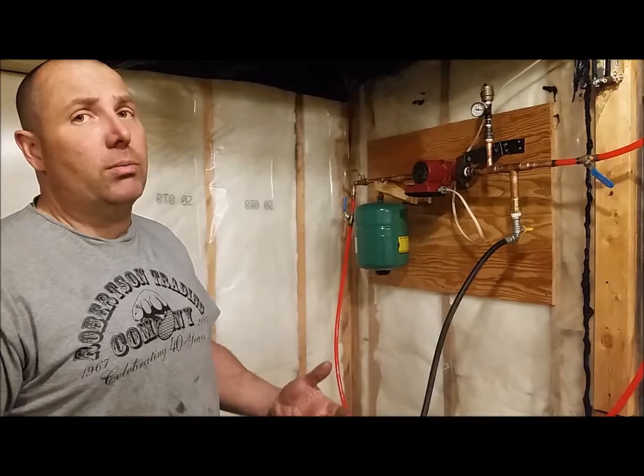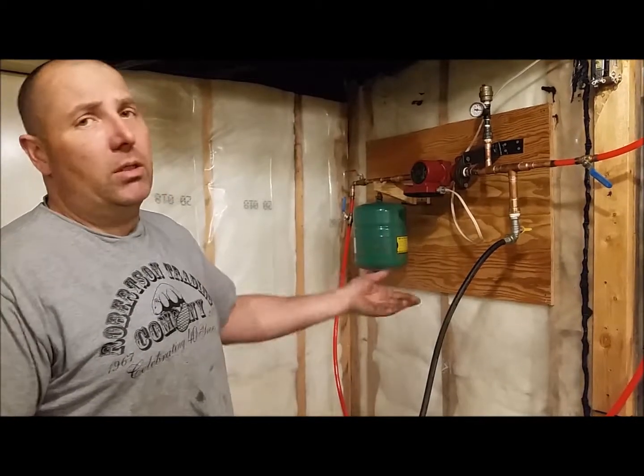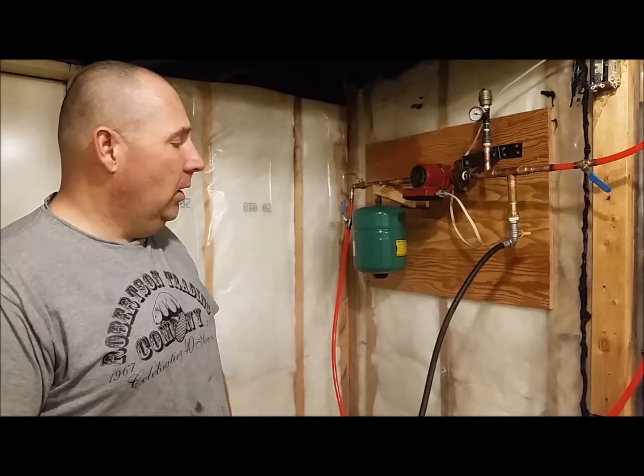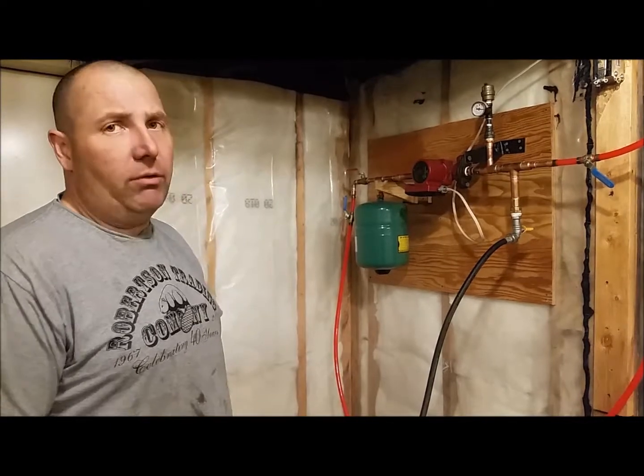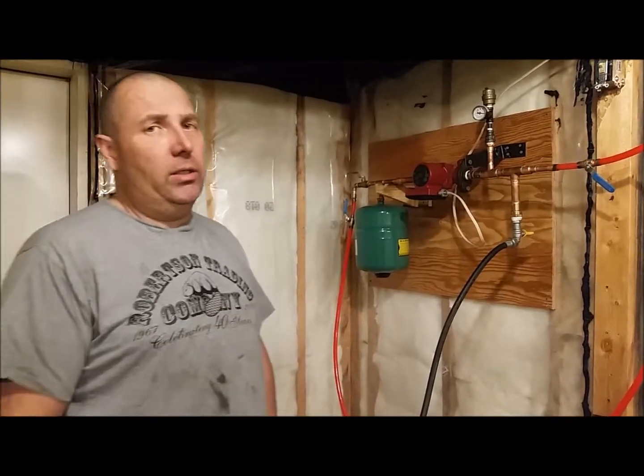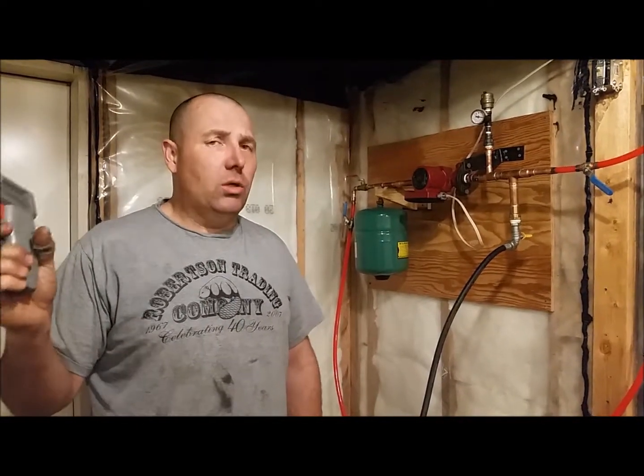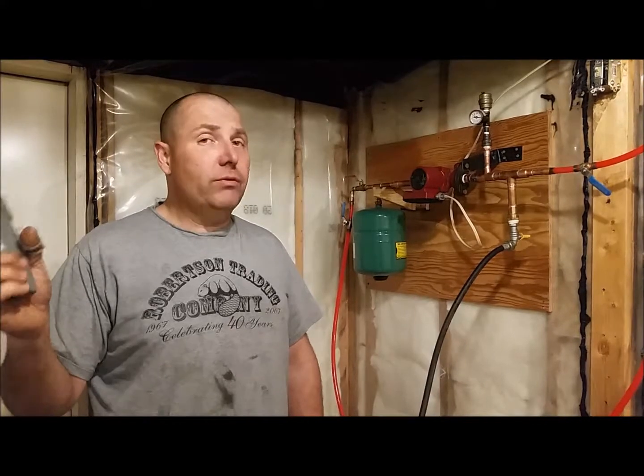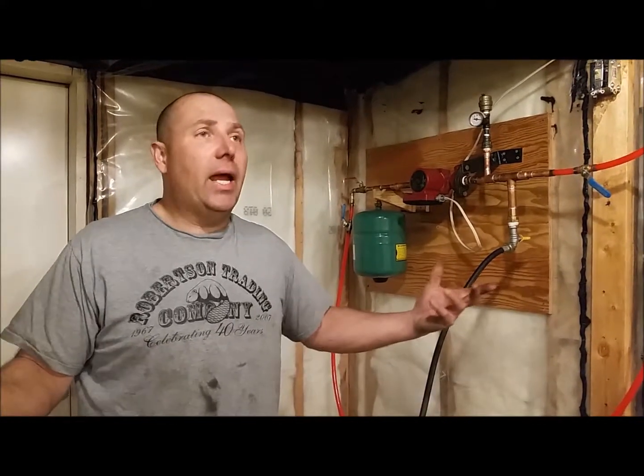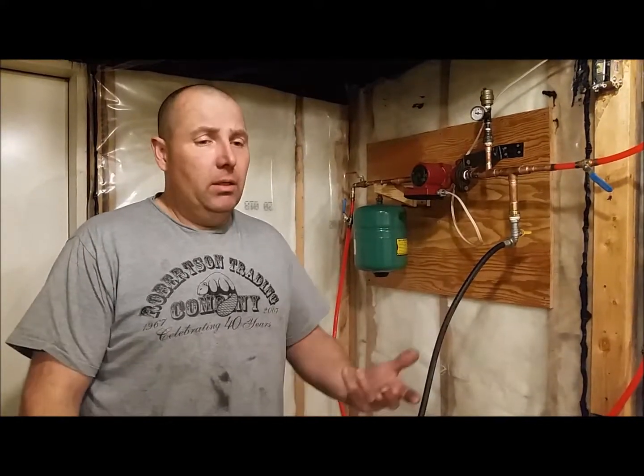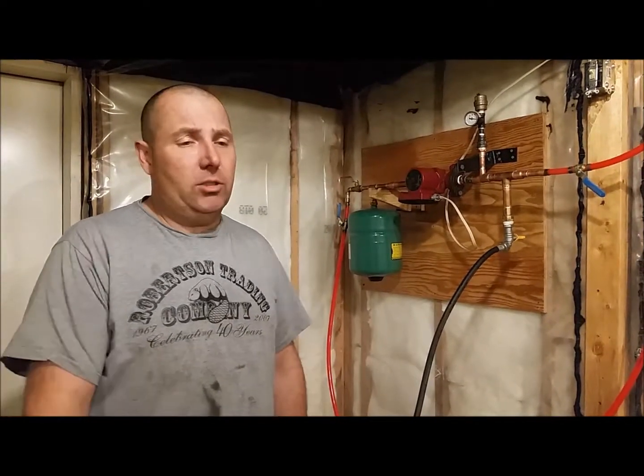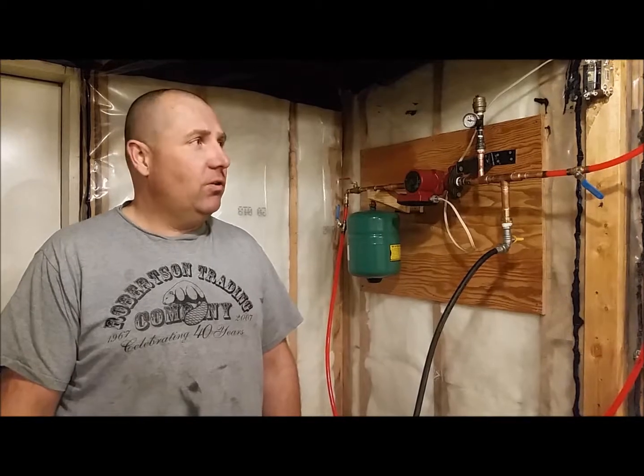As the floor absorbs more heat, the temperature will climb in the system as well. Our goal coming off the floor is in that 20 to 25 degree range. We still have the mass of the actual stove running, and it's heating the air, so that's helping maintain or increase our thermal dynamics on the concrete as well.